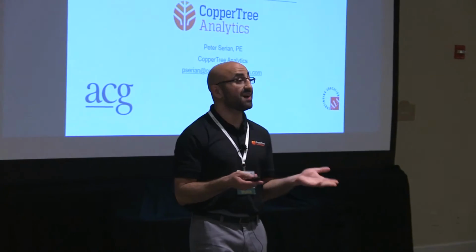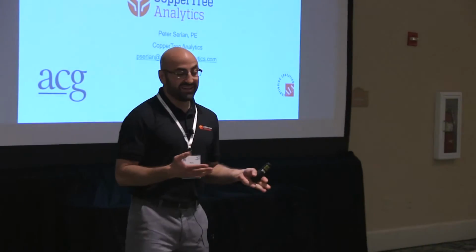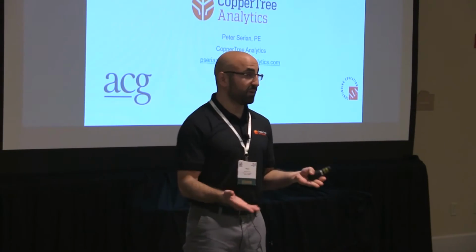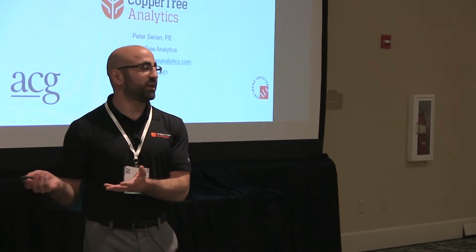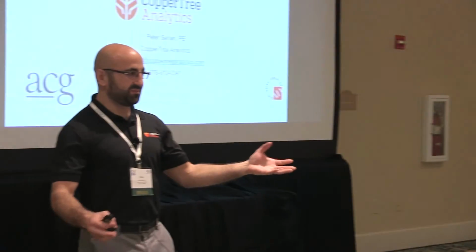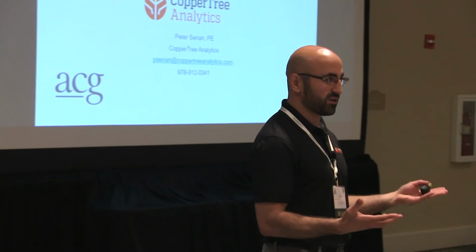Is that the trend? Yeah. So even so, it's just south of 50% our buildings still have legacy protocols, right? So if you can't talk to them, which most people can't, you're basically at the will of the controls contractor. So buildings are moving into BACnet for all new construction, any kind of renovations, all going to BACnet. Another popular thing is putting in a Tridium front end that will communicate with the legacy system and then provide sort of an open source way of getting the data and talking to that equipment. So that's where the industry is going, right?